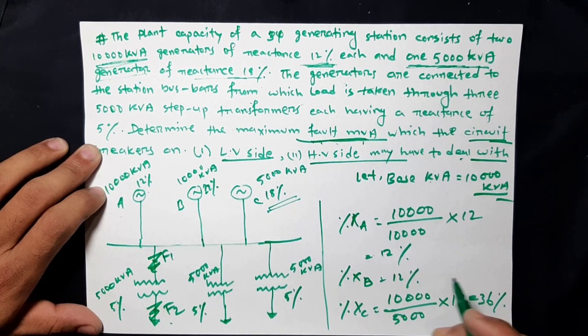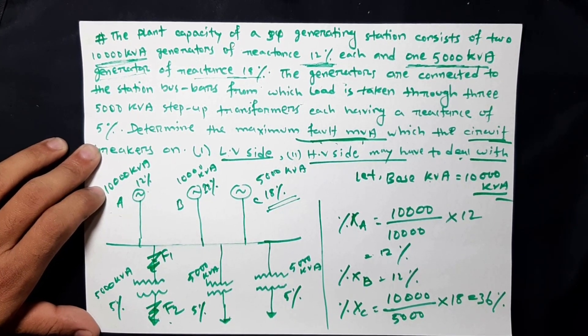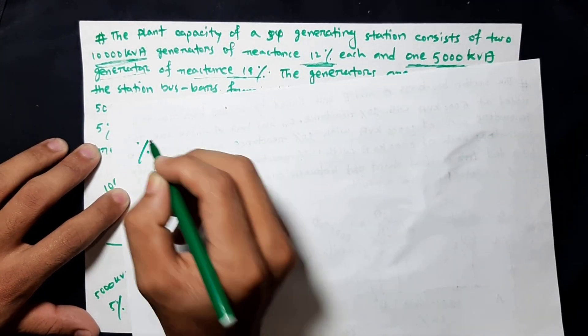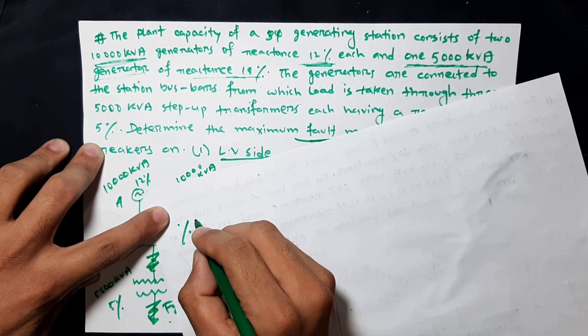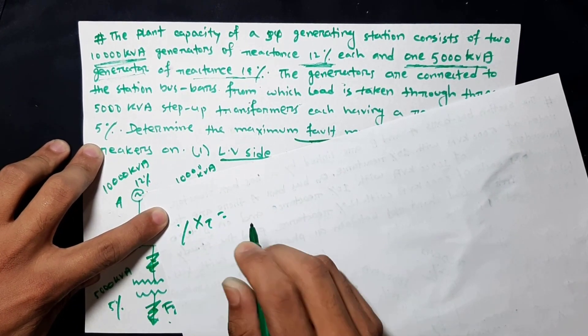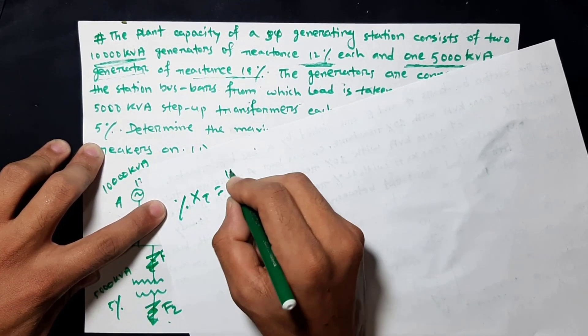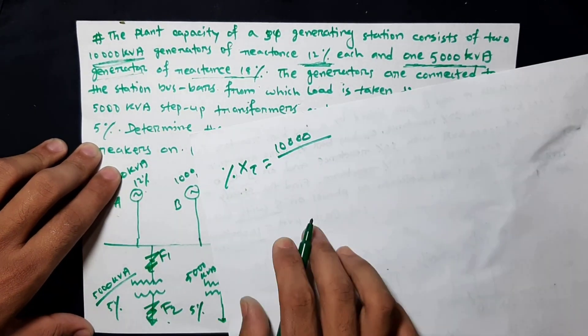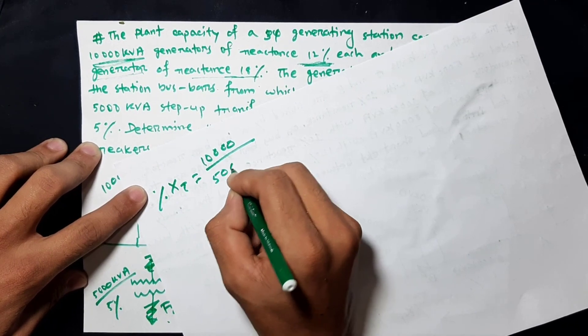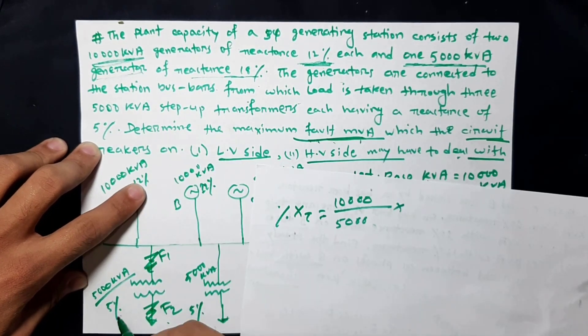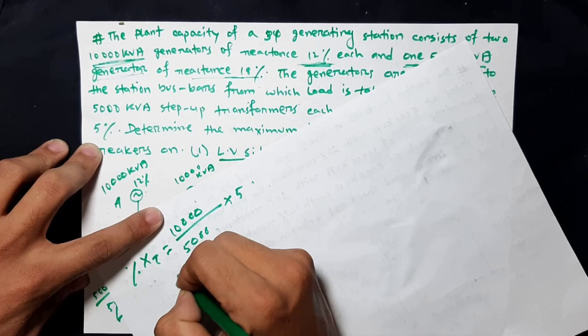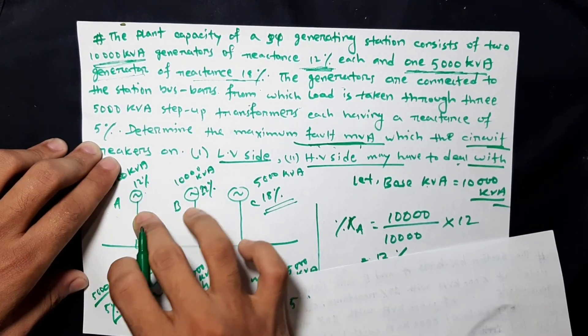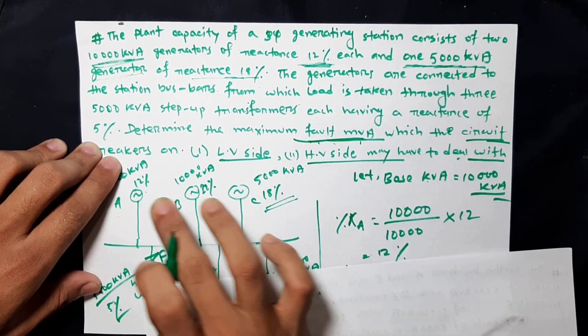Now for the transformer: percentage reactance of transformer XT at base KVA. Base KVA is equal to 10000, rated KVA is equal to 5000, percentage reactance at rated KVA is equal to 5%. The value is equal to 10%. So all values are converted to base KVA percentage reactance.